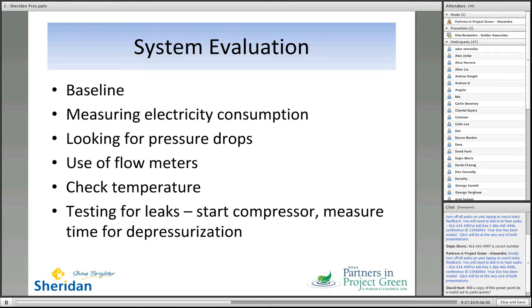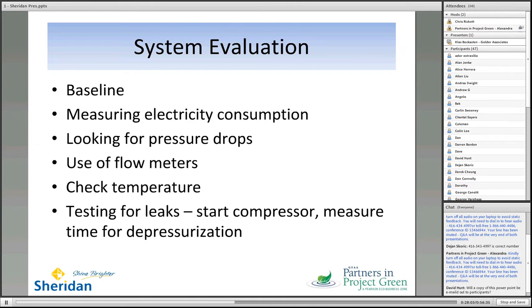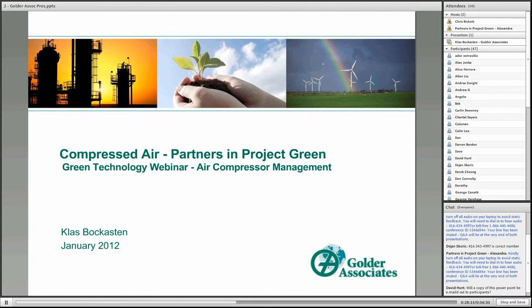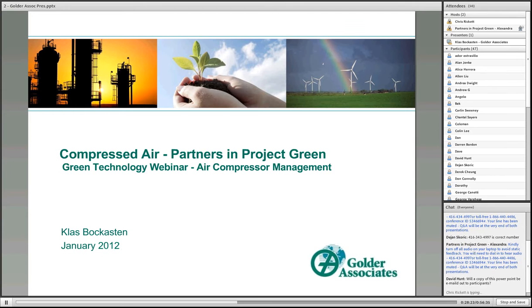Looking at different compressor technologies, compressors are typically in two categories: positive displacement, which are the most common ones, and dynamic compressors. Positive displacement used to be a number of reciprocating compressors, either single or double acting. These are oil lubricated compressors. Since the 60s, more and more rotary screw compressors have been installed and tend to be the dominating compressor used. These are of a helical screw design. There are also some rotary compressors using a sliding vane or a rotary lobe. The rotary compressors can be lubricated or oil-free. Dynamic compressors, used for heavier and larger loads, are typically centrifugals and are oil-free simply because of the nature of the compression.